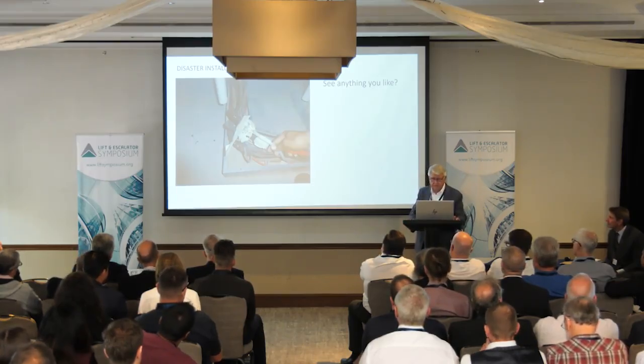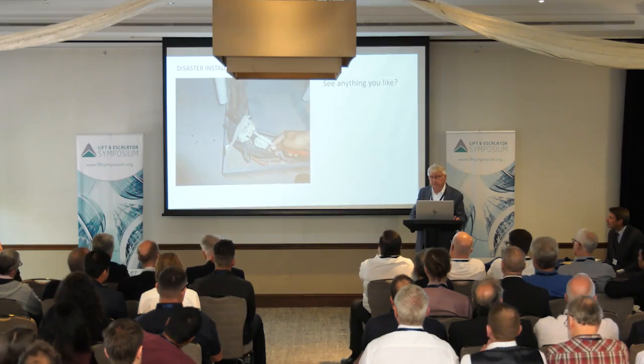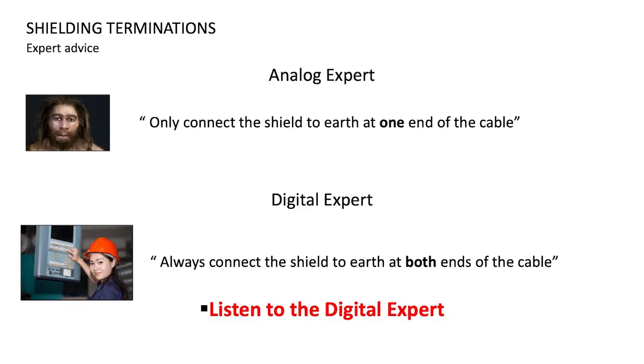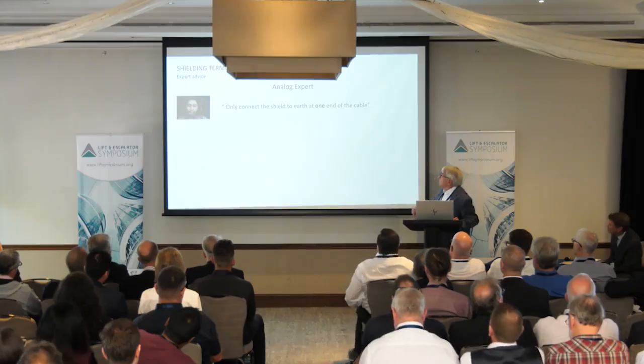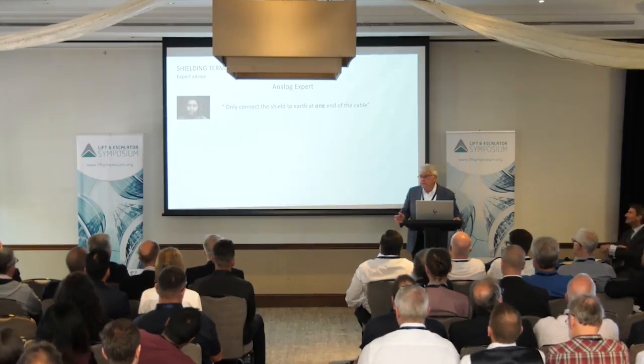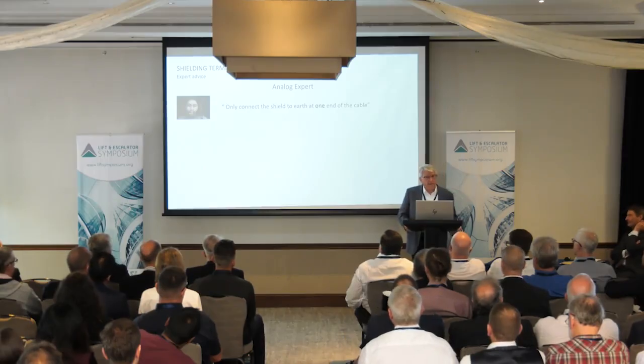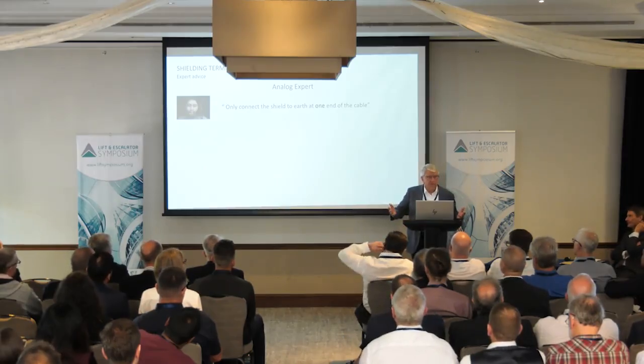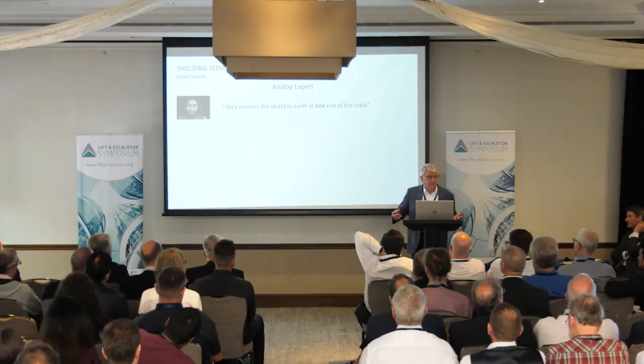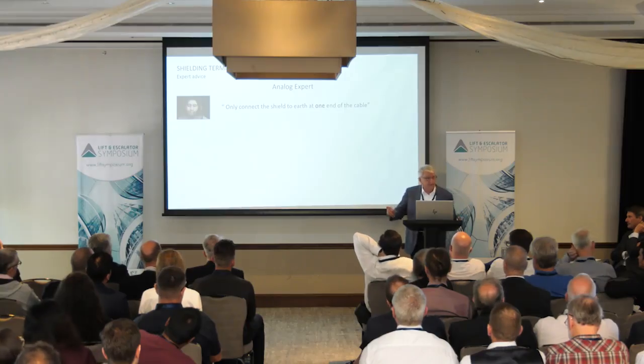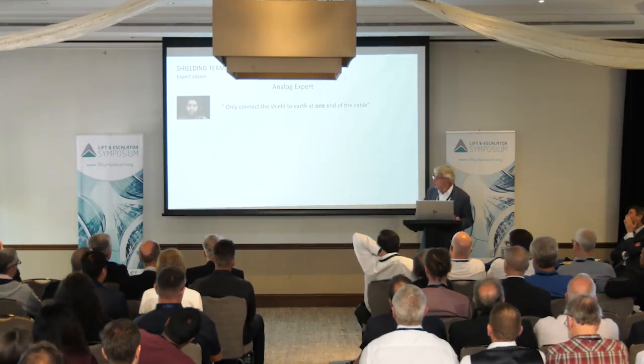There's also a lot of misinformation floating around on how to do EMC, and one common one is about shielding terminations. An analog expert will say to only connect the shield to earth at one end of the cable. That was true with analog, when you had 10 volt or 12 volt DC tachometer encoders, that was the right thing to do. But that's not the right thing to do now.